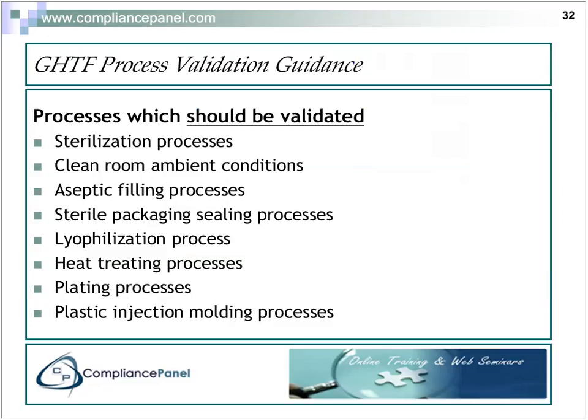So let's look at which processes do require validation. And here's a list that's in the GHTF document. Sterilization always, clean room ambient conditions, aseptic filling processes, sterile packaging sealing processes always, lyophilization processes, heat treating, plating, plastic injection molding.